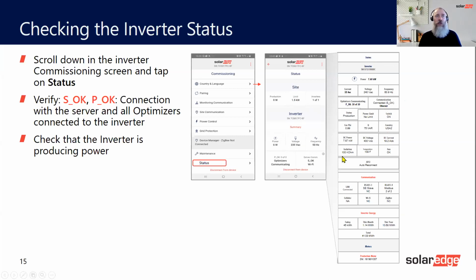Temperature, isolation value. This is one of the checks that the inverter will do. When the inverter turns on in the morning, or when it's switched on, or when it's available to start, it will do an isolation value check. Anything over 352 kiloohms, and the inverter will start. It also performs an arc fault circuit interruption check before it starts, and then it produces, and that's it. Obviously grid checks as well. It does the grid checks.